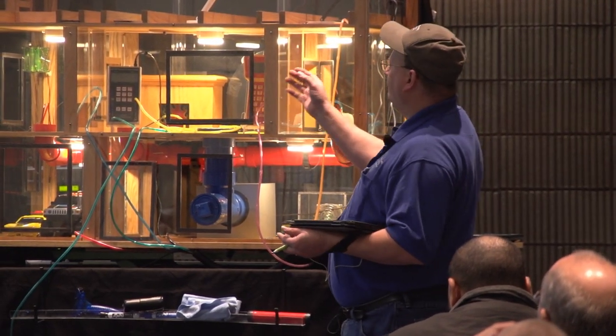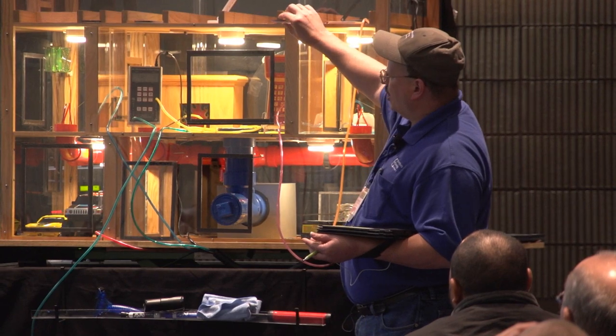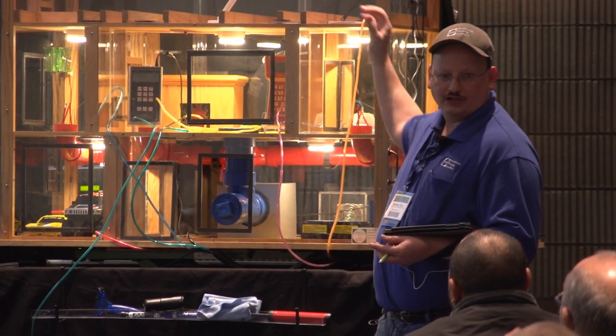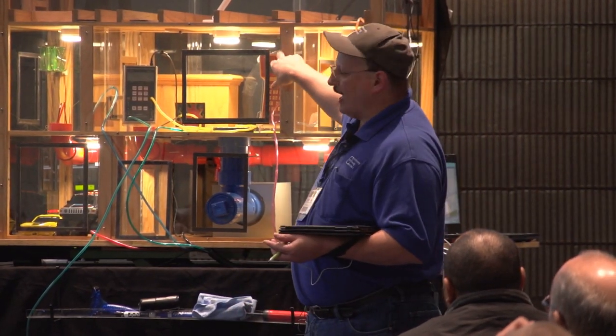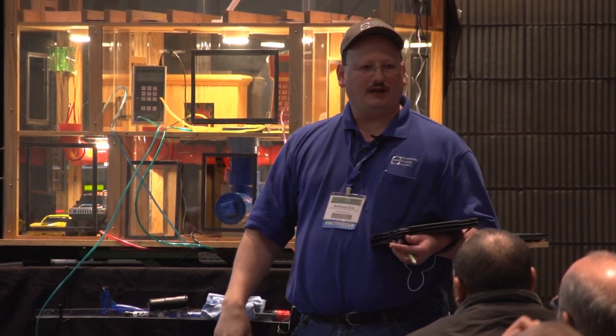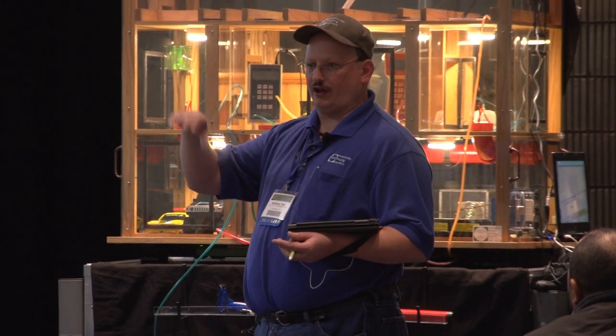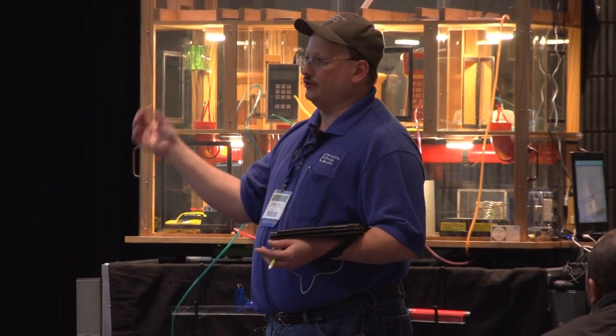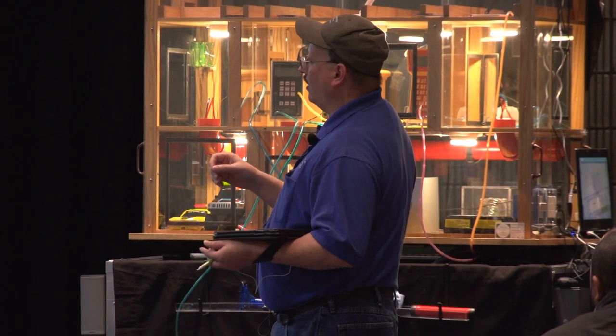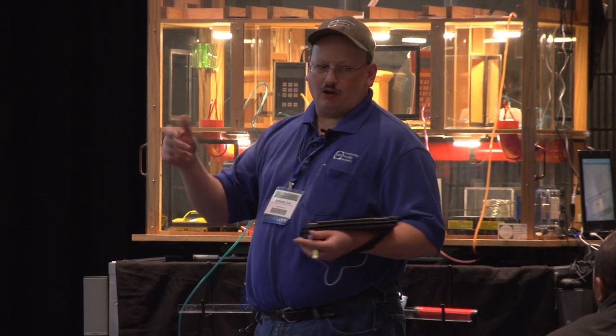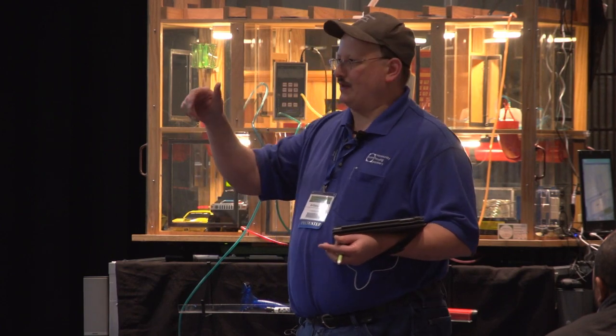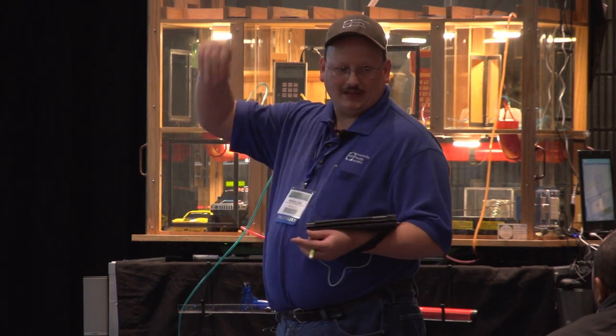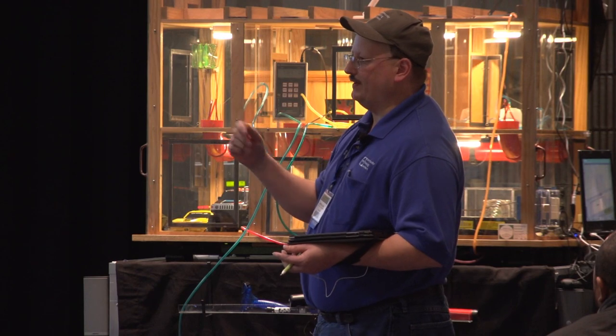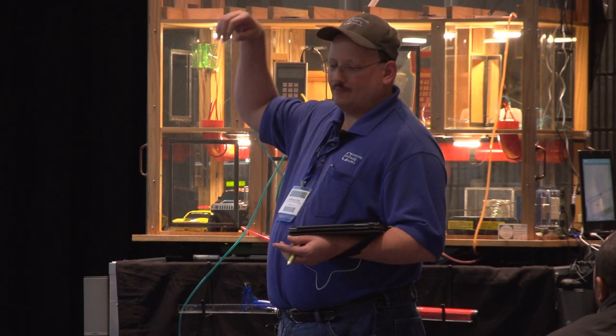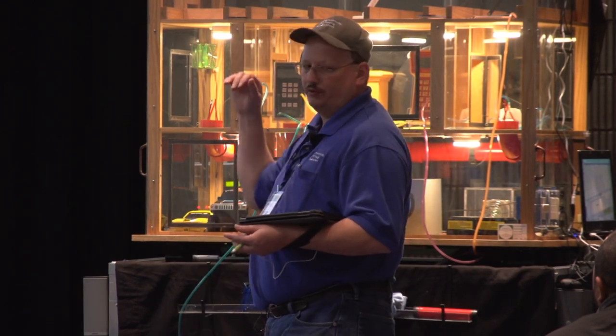If it's in the wintertime, and the top of this wall is open and the attic's cold and the blower door starts pulling air down the wall, what's going to happen to the color of the wall when you look at it with the infrared? If you're looking at it in black and white, it'll turn a darker color, won't it? Yeah. So you can use that with your blower door on. And you can just leave your blower door on. Once you've got your blower door reading, you just keep it at about 30 pascals or so, just enough to keep a pressure difference, and walk around with that infrared. And if there are leaks up into the attic, it'll be pulling the air down.